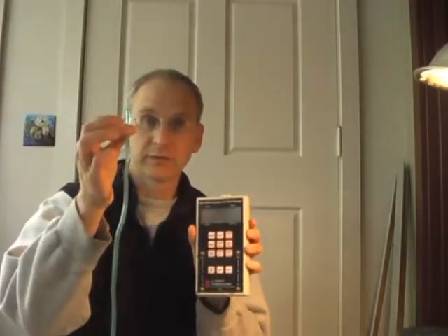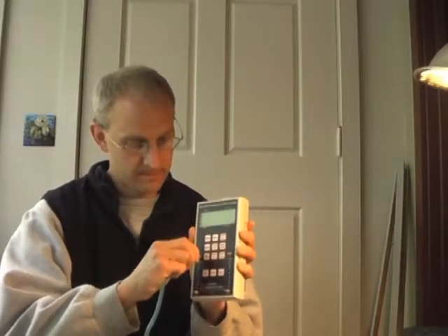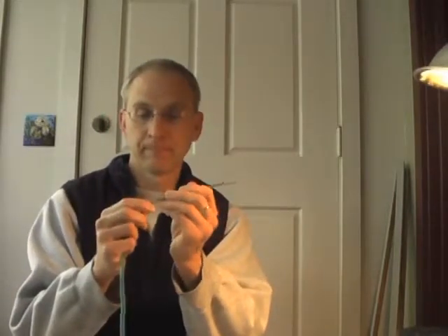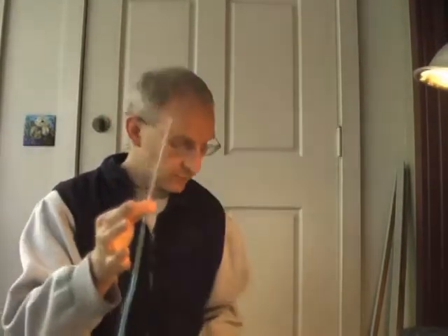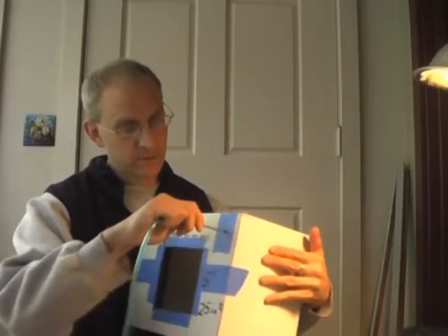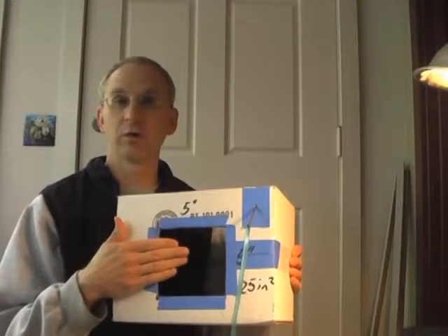We'll take our digital manometer and a hose, and attach the hose to the input tap on channel A. On the other end of the hose, we're going to insert a static pressure probe, and use this to penetrate the flow box through a port. We're able to measure the difference in pressure across this hole when the fan is on, and we will see that on channel A. When we turn our digital manometer on, we keep it on the default setting, which is Pressure-Pressure.